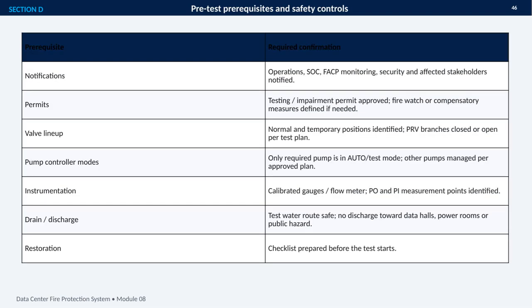This slide covers the prerequisites and safety controls that must be confirmed before pre-testing the fire protection system. The goal is to make sure the test is controlled, observable, and reversible, without creating an avoidable risk to the data center. No test should begin until the required notifications and permits are in place. That includes operations, the Security Operations Center, fire alarm control panel monitoring, security, and any affected stakeholders. If the system will be impaired, the approved permit must also define a fire watch or other compensatory measures.